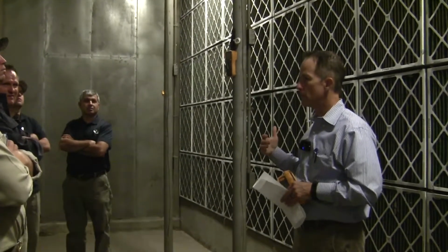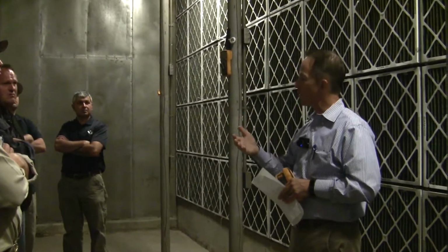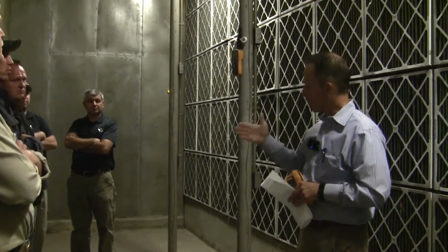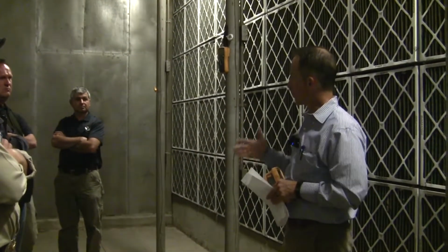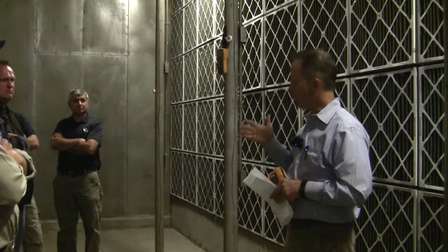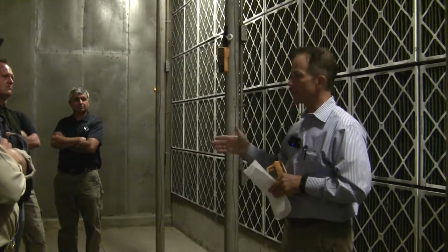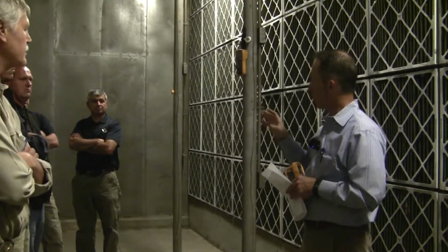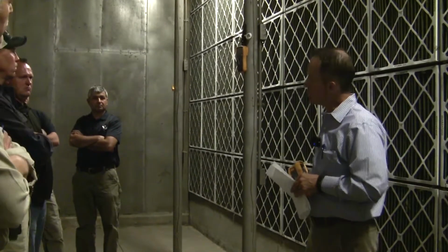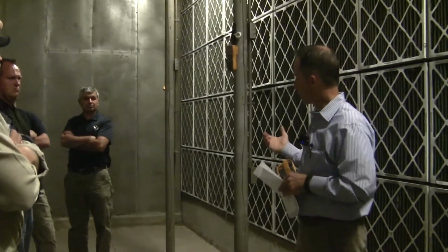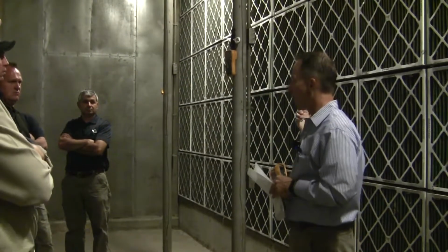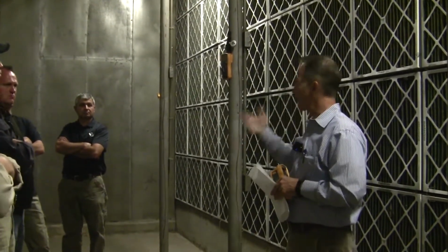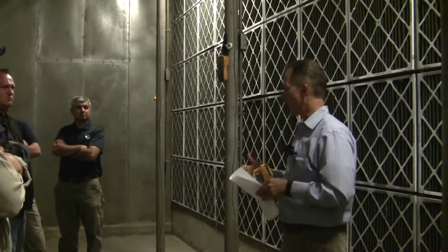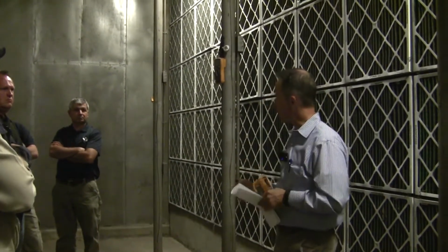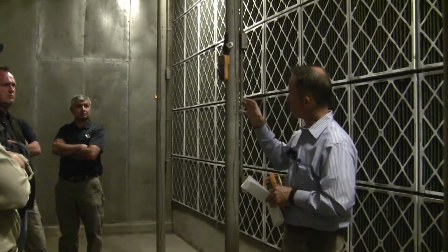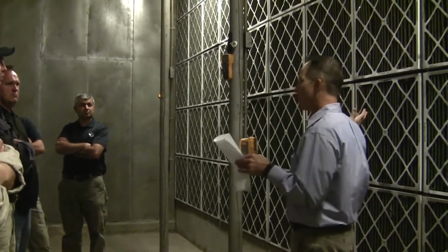So you have better control on the building. Okay, so it provides better control, and ultimately, instead of us lowering a set point, say we're reading a couple degrees off, we'd rather have the right temperature, and we'd also not want to put too cold of air down the duct, because then you just have to reheat it somehow, whether it's a reheat coil or hot deck to blow hot air in there. We have buildings where we have to run the hot deck all year round, right? And if we can minimize that or even shut it off in the summertime, that'll save us a lot of money. So making sure your system is calibrated, especially on the big equipment, right?